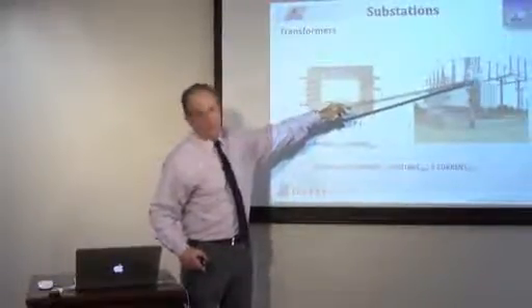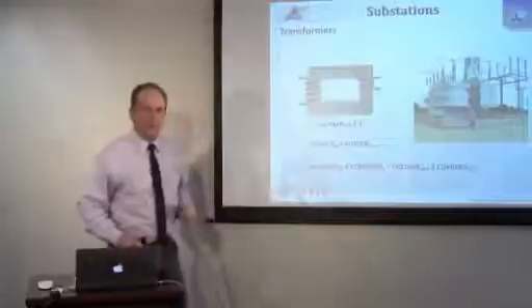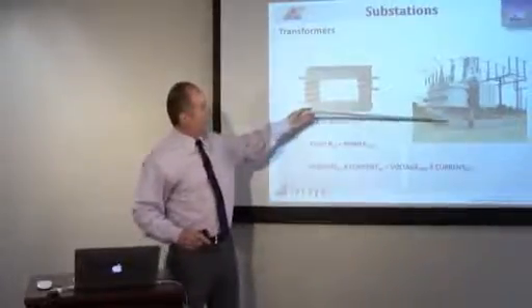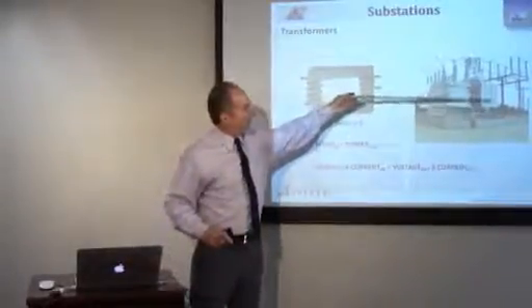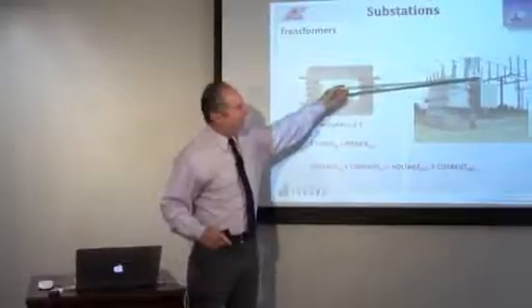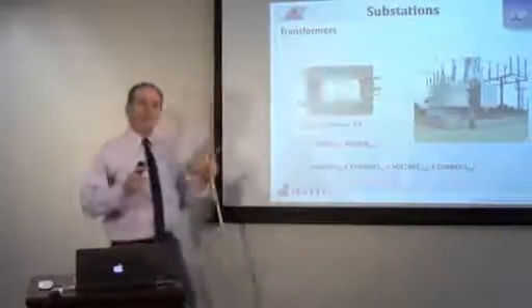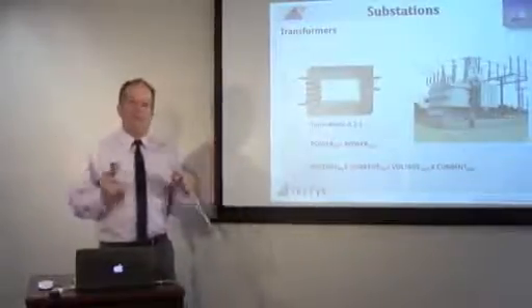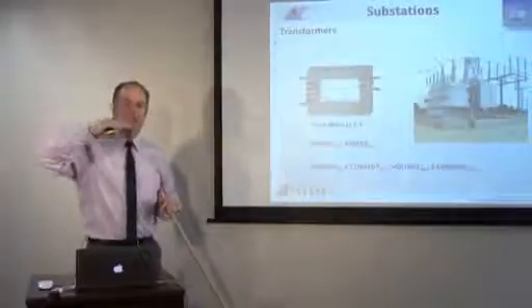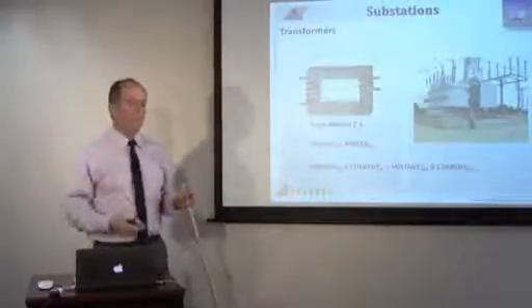Now this tank up on top is called the conservator tank. You fill the transformer all the way up with oil, all the radiators all the way up, and you fill the conservator up to about halfway. So when the transformer expands and contracts in cold and hot weather and loaded and unloaded conditions, the oil level in the conservator goes up and down, and that's how you keep the transformer filled with oil.